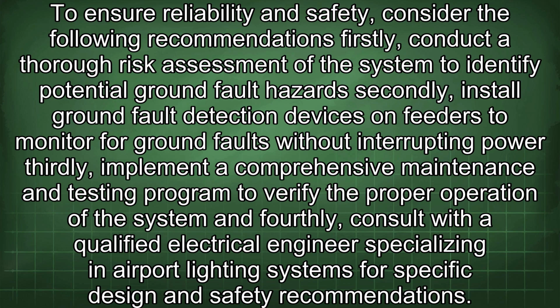Firstly, conduct a thorough risk assessment of the system to identify potential ground fault hazards. Secondly, install ground fault detection devices on feeders to monitor for ground faults without interrupting power. Thirdly, implement a comprehensive maintenance and testing program to verify the proper operation of the system. And fourthly, consult with a qualified electrical engineer specializing in airport lighting systems for specific design and safety recommendations.